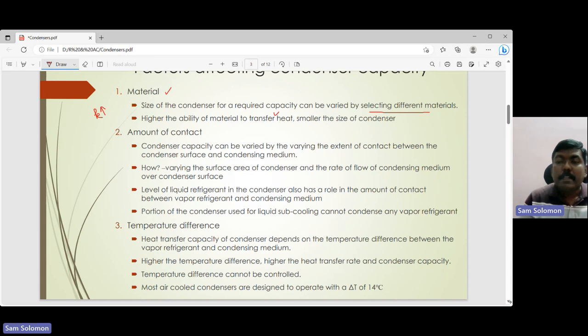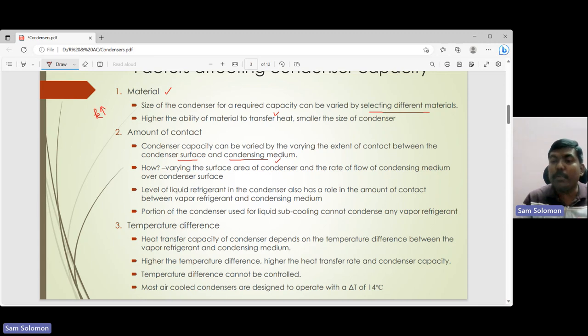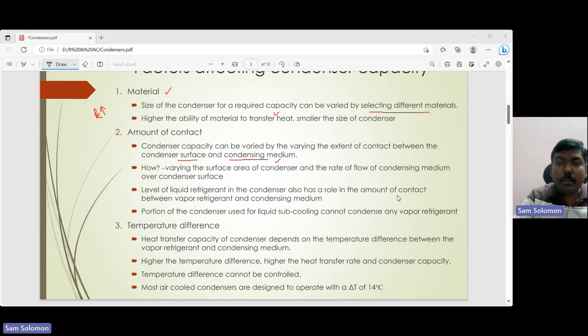The second factor is the amount of contact, which depends on the heat transfer area. Increasing the surface area of heat transfer gives a higher heat transfer rate, which can be achieved using finned tubes. The amount of contact between the condenser surface and the refrigerant vapor matters. You can either increase the condenser surface area or decrease the mass flow rate of the refrigerant, so it stays in contact with the condenser surface longer and removes a larger amount of heat.